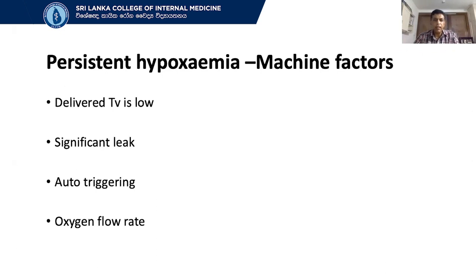One thing is now we know that there is a tidal volume. So when you go back to advanced settings, or you see in the main setting, you see the tidal volume. Usually we expect at least 6 ml per kg of a tidal volume delivered to these patients, and you need to see the delivered tidal volume. If the delivered tidal volume is low, you can increase the PEEP, or you can increase the TI, right? Timed inspiration. So you increase the inspiratory time. That is where you need the advanced setting.